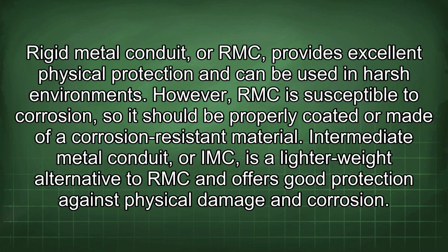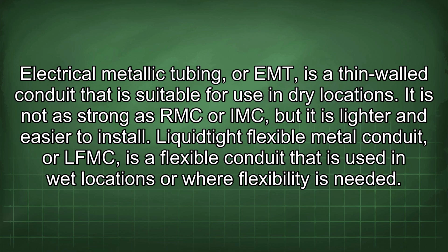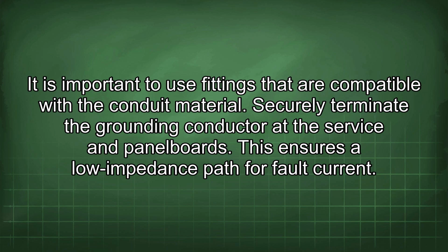Intermediate metal conduit, or IMC, is a lighter weight alternative to RMC and offers good protection against physical damage and corrosion. Electrical metallic tubing, or EMT, is a thin-walled conduit that is suitable for use in dry locations. It is not as strong as RMC or IMC, but it is lighter and easier to install. Liquid-tight flexible metal conduit, or LFMC, is a flexible conduit that is used in wet locations or where flexibility is needed. It is important to use fittings that are compatible with the conduit material.